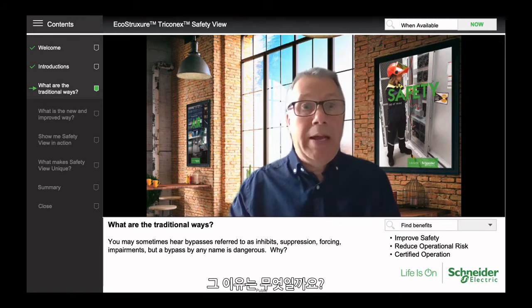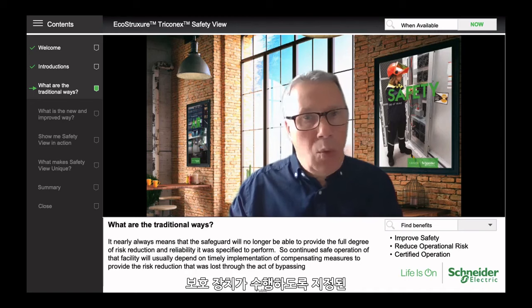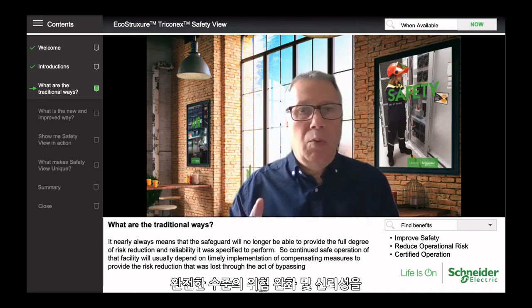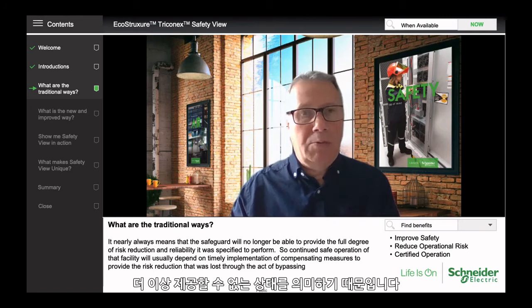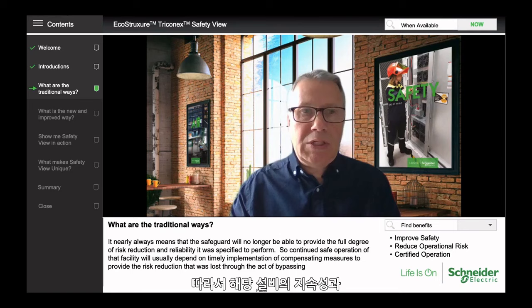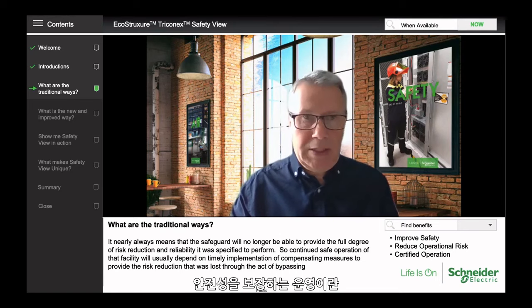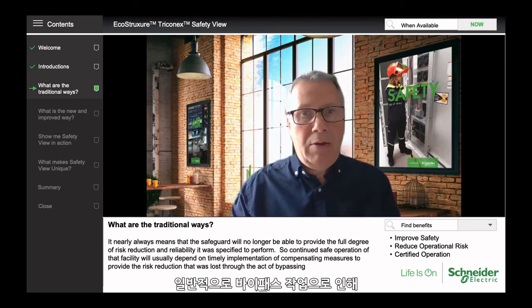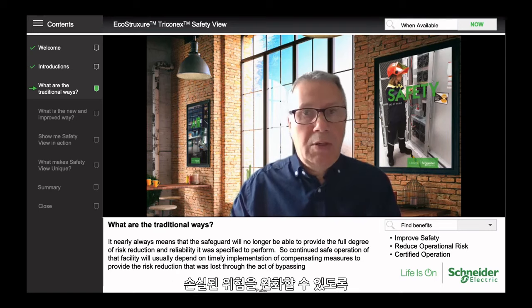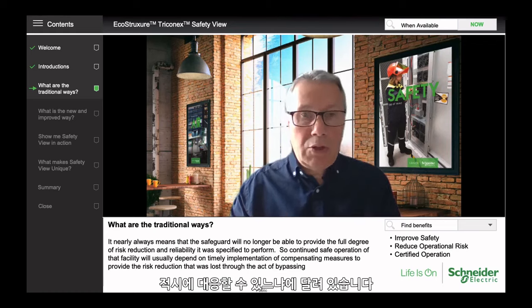Why is a bypass dangerous? It nearly always means that the safeguard will no longer be able to provide the full degree of risk reduction it was specified to perform. So the continued safe operation of that facility will usually then depend on the timely implementation of compensating measures to provide the risk reduction that was lost through the act of bypassing.